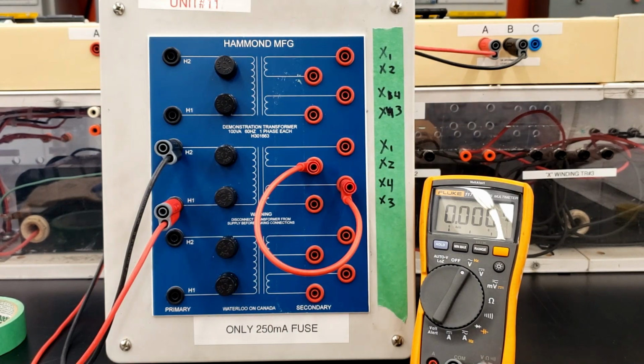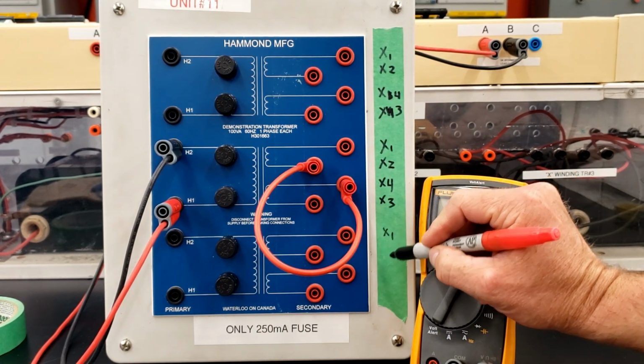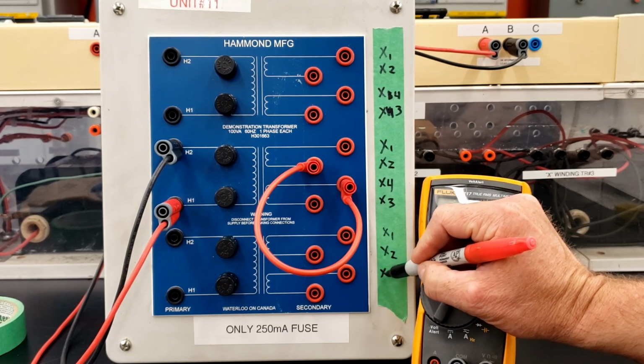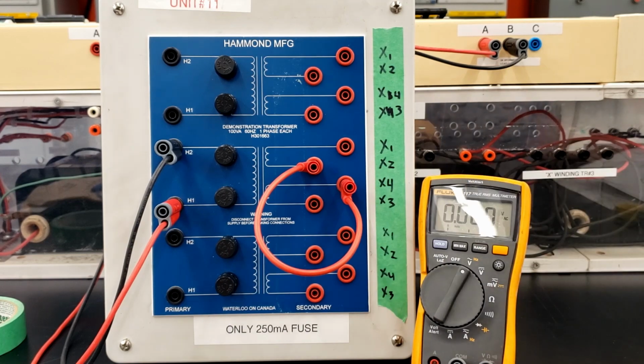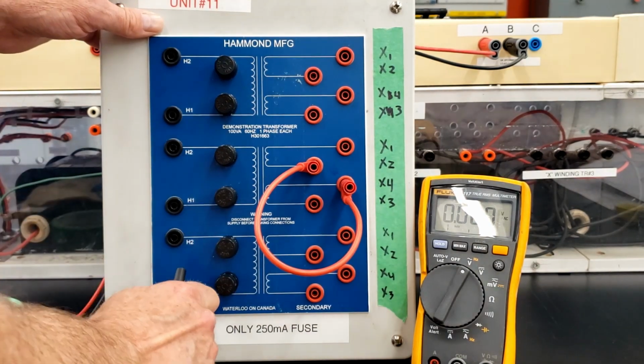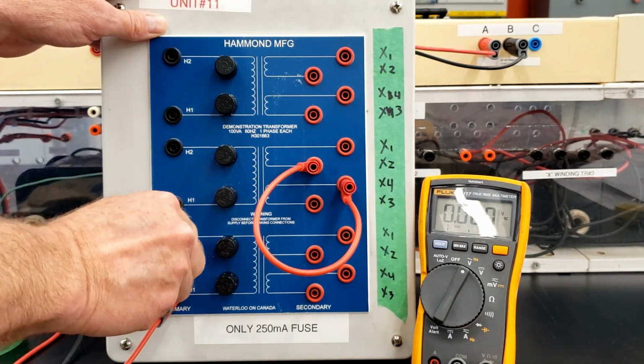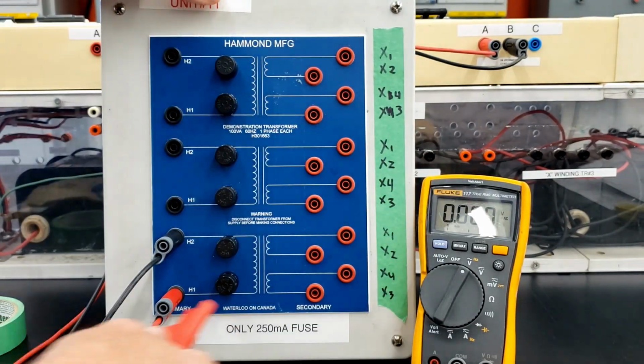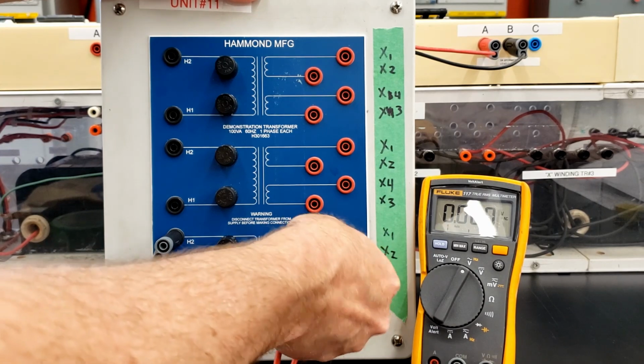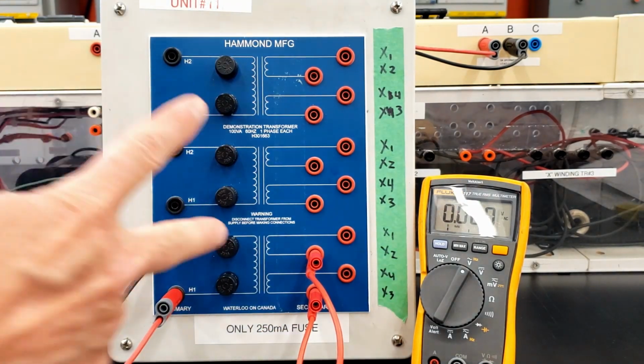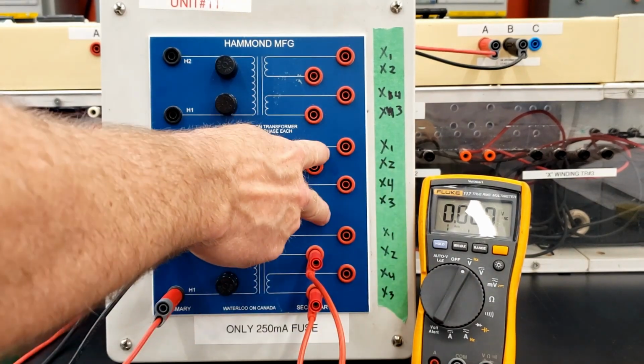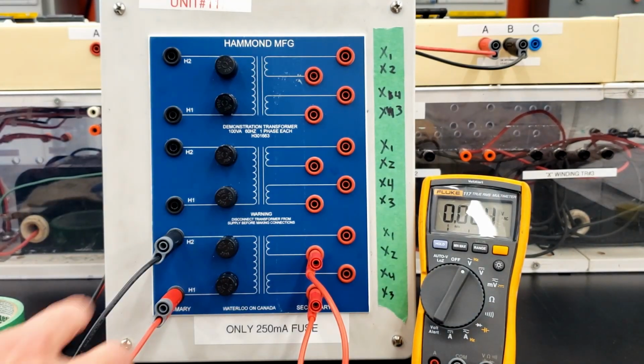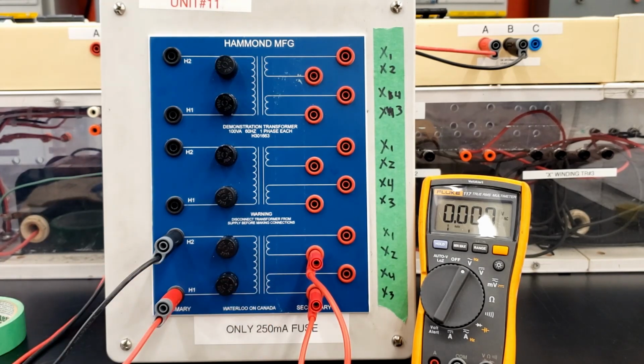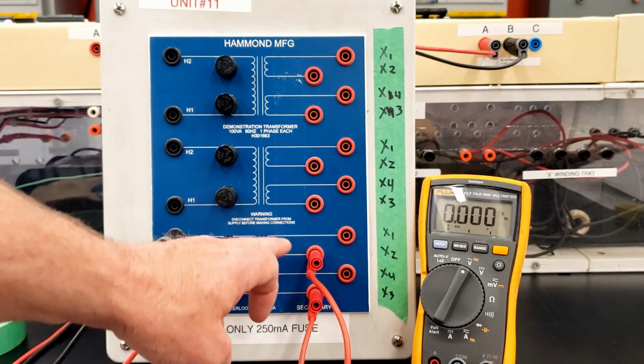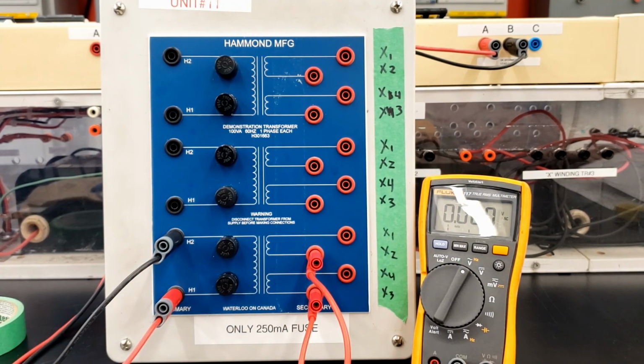I'm thinking whoever wired this up kept this the same, so this guy is going to be 4 and this guy is going to be 3. Again, I'm bringing my voltage down to the third transformer, keeping that polarity the same. I'm jumpering my X2 and X3, so same polarity to the primary means the secondary windings are all going to be in phase. I'm not changing this polarity, and now I'm seriesing up the secondary so I'd have 120 plus 120, giving me 240 volts on the secondary side.